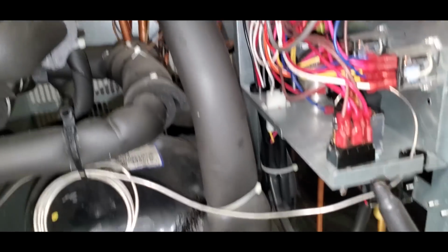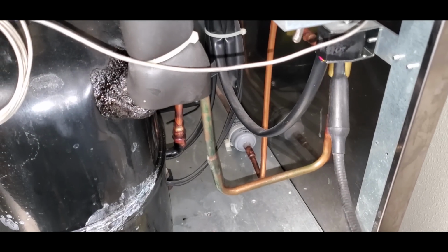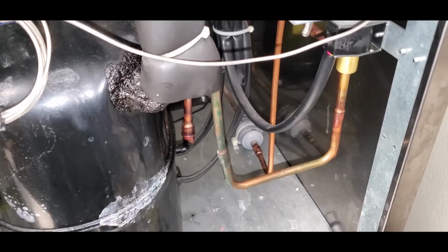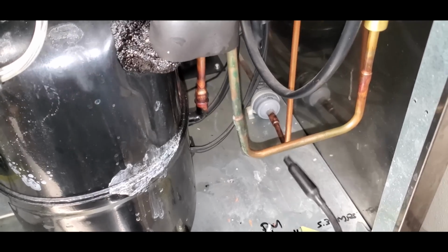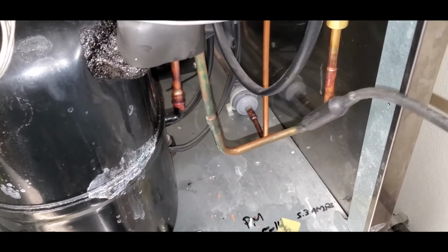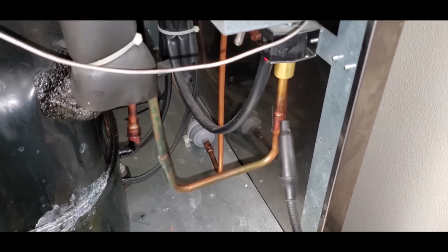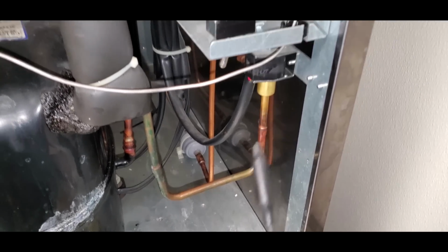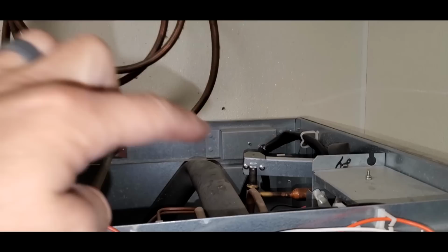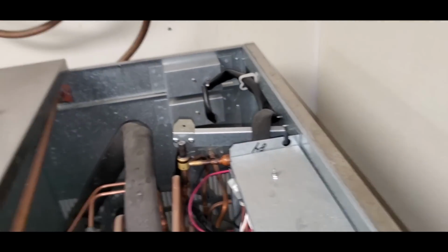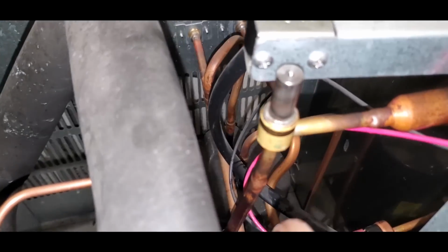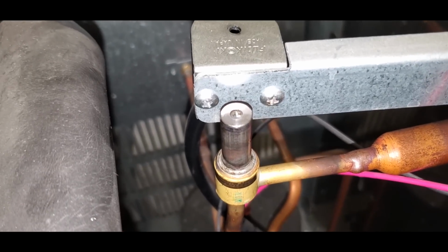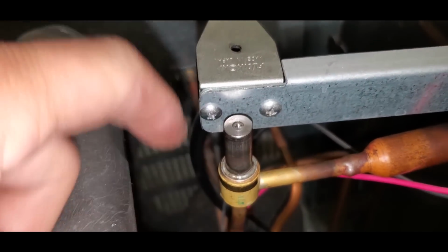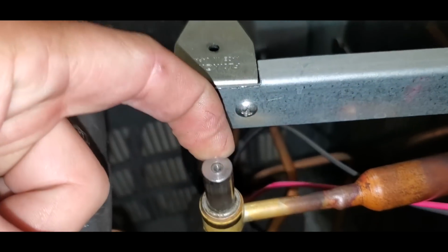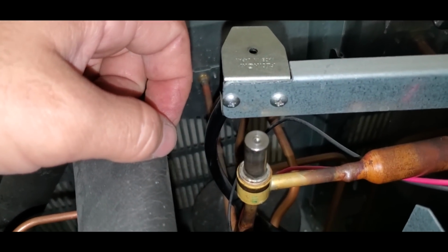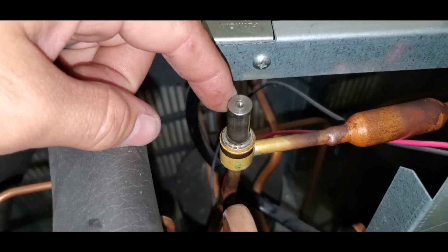And I can see visible oil on it, but it's interesting, I can see oil on this valve too, and I'm picking up a leak right in here. On this one for sure. These solenoid valves leak. It's very common for them, so I'm gonna put some bubbles on this one over here. For the life of me, I might see a few micro clusters, but that is it. There's nothing popping up on this one, but I'm telling you, there was oil all over this valve, which, like I said, there's a history of these things leaking, so if I change that liquid line solenoid valve, which is the one down below, I'm probably going to change this one too, just because of the high leak rate that they have.